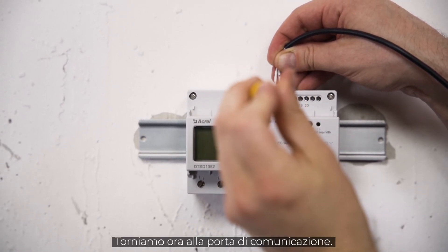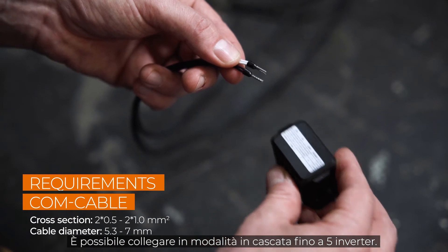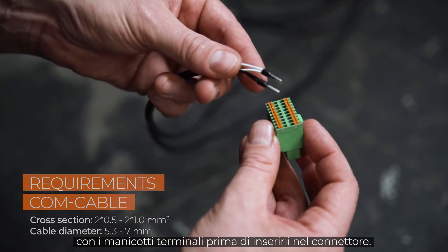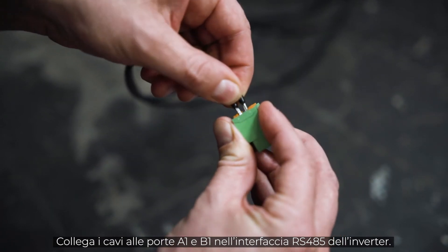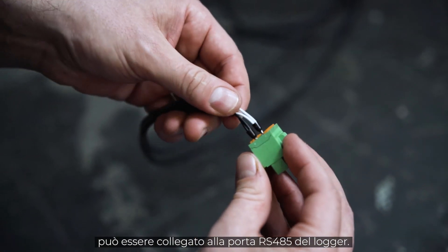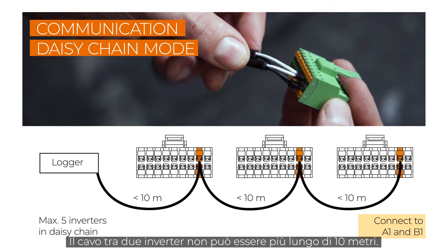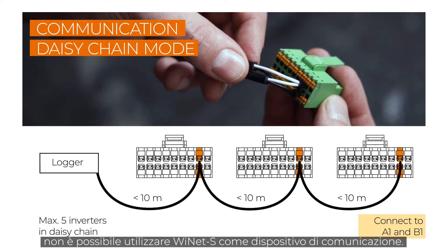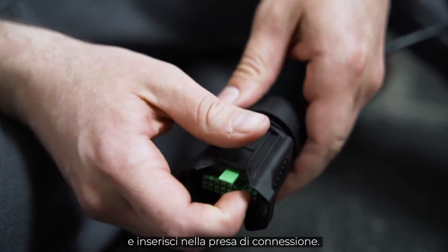Now let's jump back to the communication port. A maximum number of 5 inverters can be connected in daisy chain mode. If necessary, you may have to fit the cables with end sleeves before you push them into the plug. Connect the cables to ports A1 and B1 at the RS-485 interface of the inverter. The first inverter in daisy chain mode can be connected to the RS-485 port of the logger. The cable between two inverters should be no more than 10 meters. When daisy chain mode is being used, the WiNet-S can't be used as communication device. Plug everything together, screw it and plug it in.